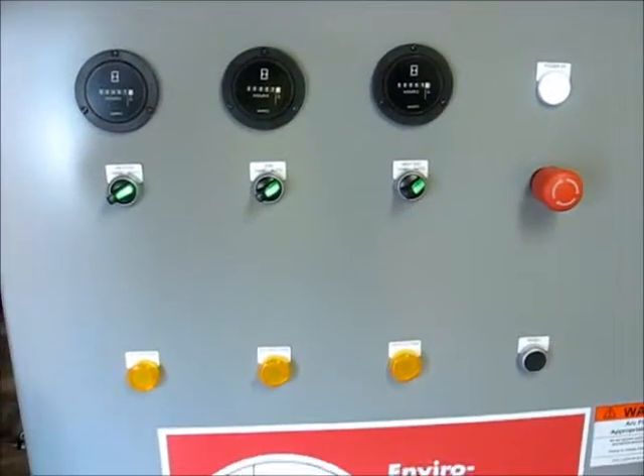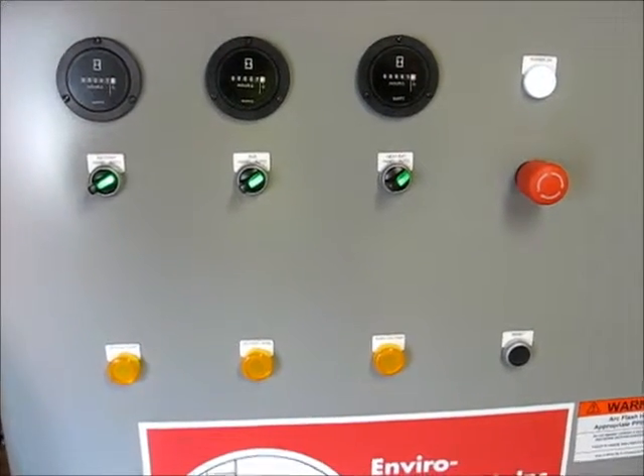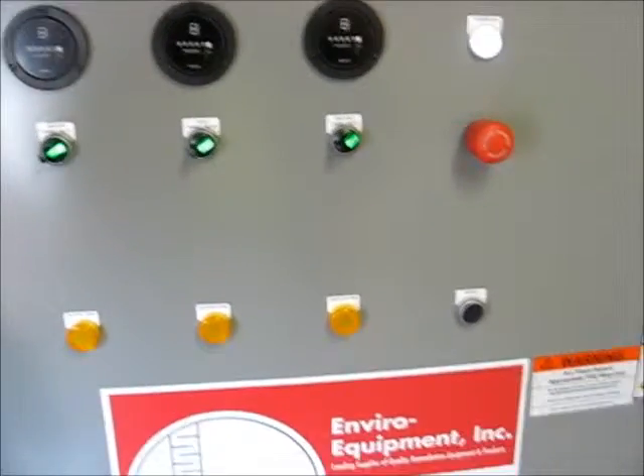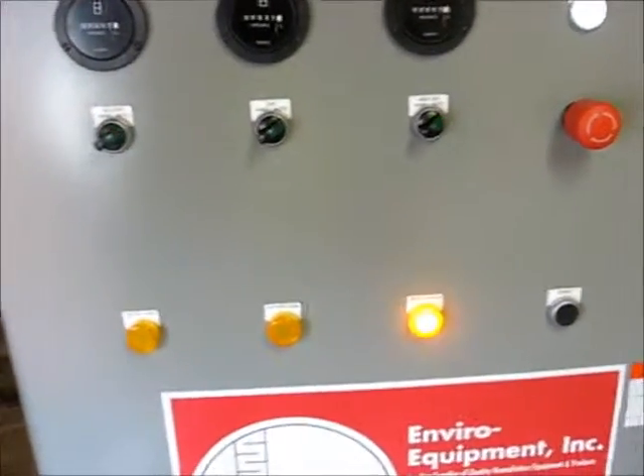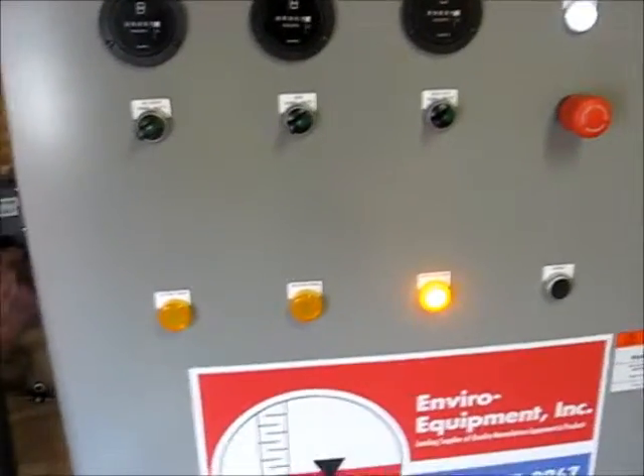This is the FBE room temperature alarm going off — actually it's the air sparge room temperature going off. Everything is on. Air sparse temperature is going down. It shuts off and we get a room temp high light. We're going to put it back to where it's supposed to be — 104 degrees.